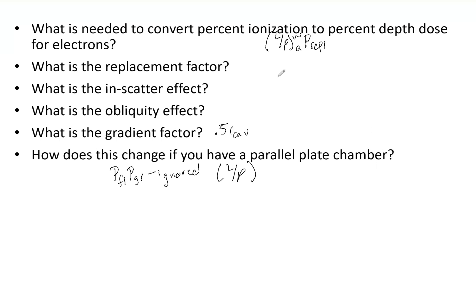Ultimately what we have as a final conclusion is our percent depth dose in water is equal to our percent depth ionization (again that's going to be in water, that's where you measure this) that is going to be multiplied by L over rho of water to air multiplied by the replacement factor at your depth.